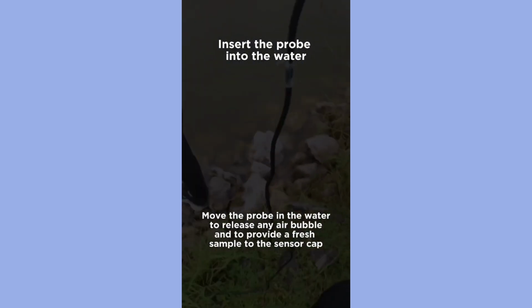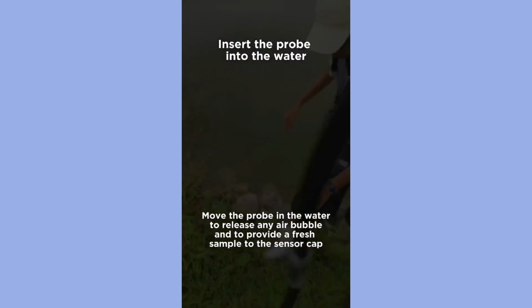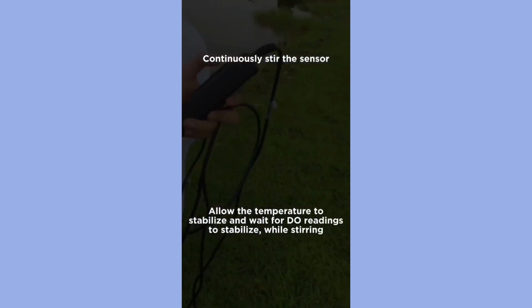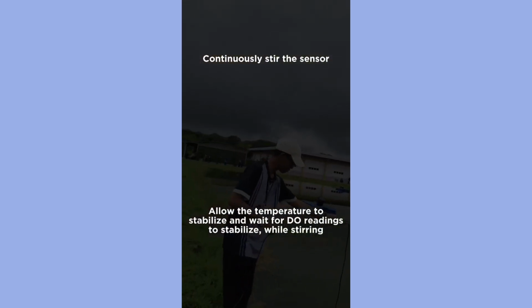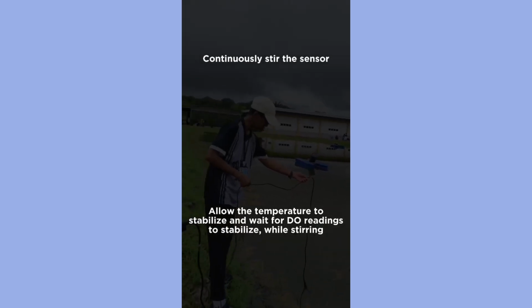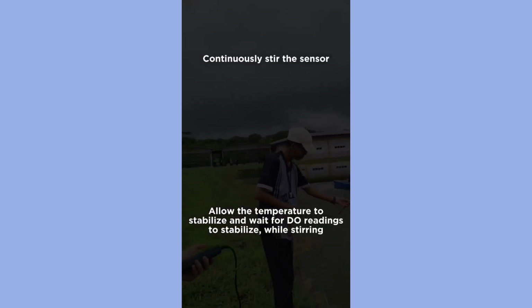Next, insert the probe into the water and move the probe in the water to release any air bubbles and to provide a fresh sample to the sensor cap. Then continuously stir the sensor, allow the temperature to stabilize, and wait for DO readings to stabilize while continuing stirring.